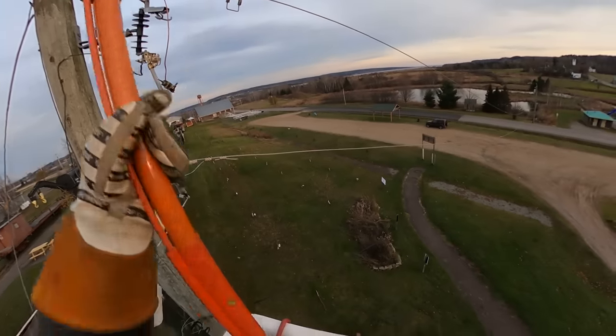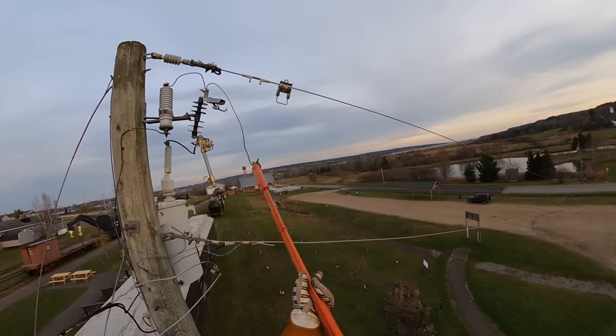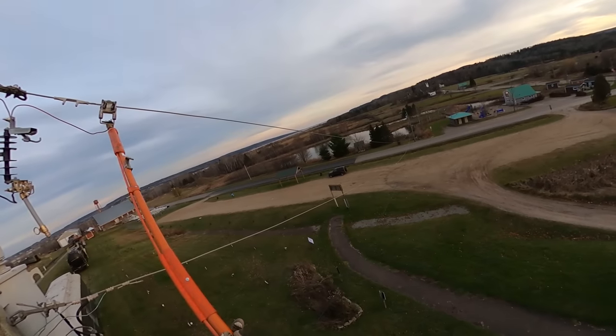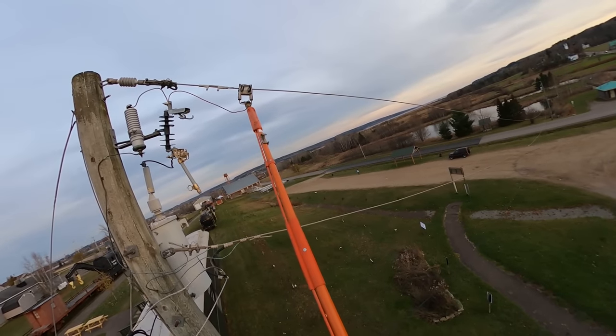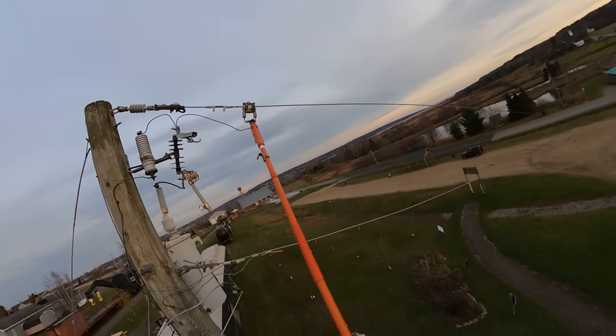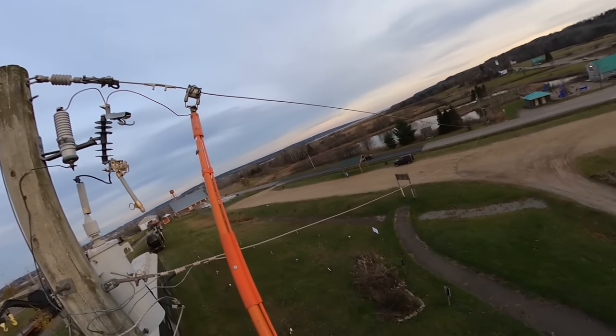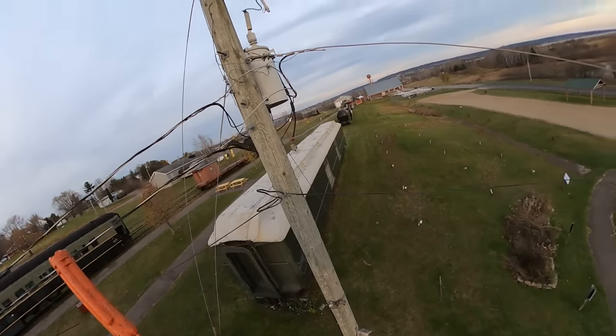We've got our stirrup on, and now we're going to move into position. I'm going to move as far away as I can because we are going to be energizing that lightning arrester again — which is a high-resistance path to ground. There is a very small chance it could fail; if it does, you don't want to be anywhere near that. That's why I much prefer — and most companies do install — those lightning arresters on the transformer now, so you're a long ways from the pole when you close it. Once you tighten those tap clamps and it's all the way tight, you want to shake the stick around a little bit and give it a flick to make sure it is fully seated in the jaws of the tap clamp.